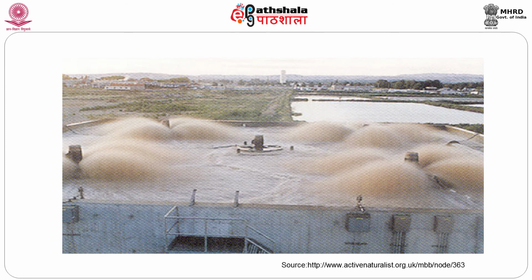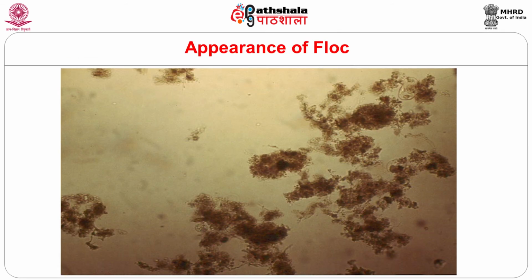This is the aerial view of the aeration tank. So, this is the biological floc that will be generated during biochemical transformation. During biological transformation, whatever substrate is loaded into the biological system will be converted into biological mass. I have already pointed out, if you investigate the mass balance analysis of an aerobic system, roughly 50% of the COD is transformed into biological mass, and 50% of the energy will be wasted in the form of heat energy.